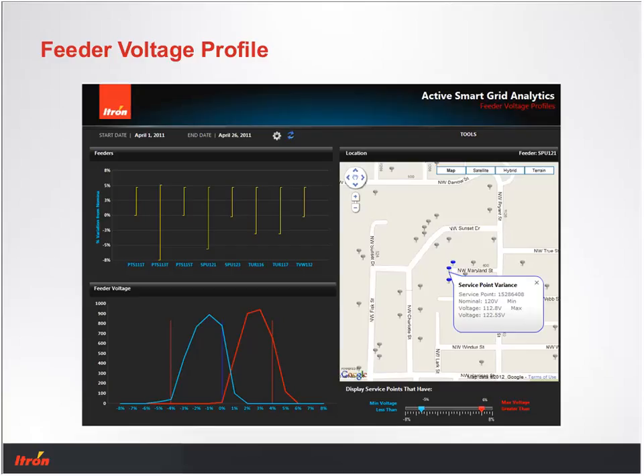So what I'm going to do is take a look at that first service point. If we go back, it was the middle service point that was the lowest. Now let's take a look, and we can see the parameters around that particular one, and we can see that the low voltage was 112.8, and that is below our tariff. So that's not good. We really don't want to see that at all.